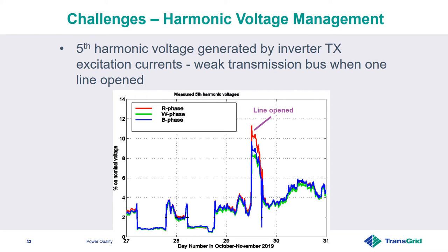This is the same information we saw in the previous slide, that is, fifth harmonic voltages generated due to inverter transformer excitation current at the weak location. The x-axis is zoomed in to clearly demonstrate how harmonic voltage is increased by further weakening the network. You can see here harmonic voltage shoots up to 10 to 11% when one line connected to the weak location is opened. When the line is open, the harmonic impedance is further increased, causing an increase in harmonic voltage.